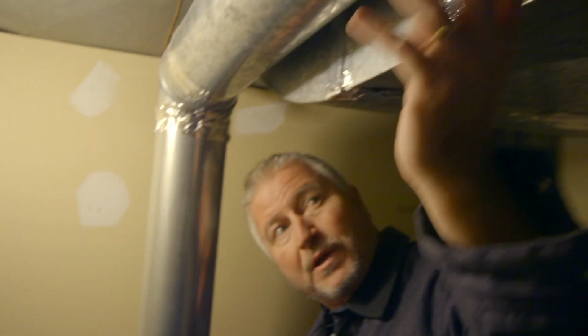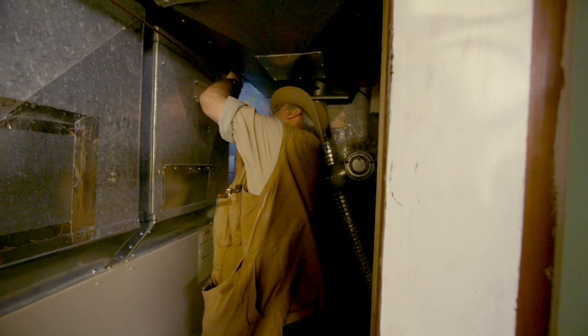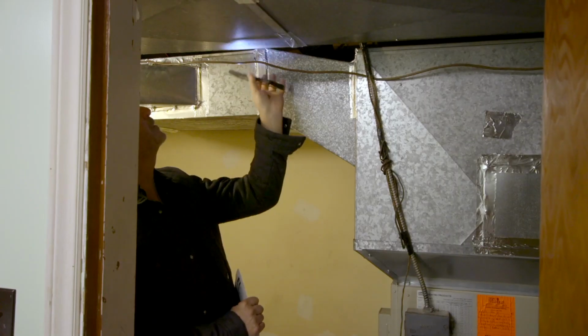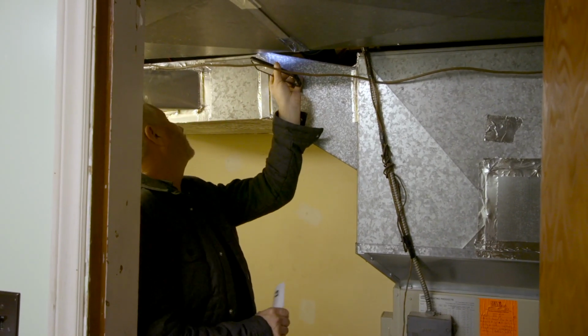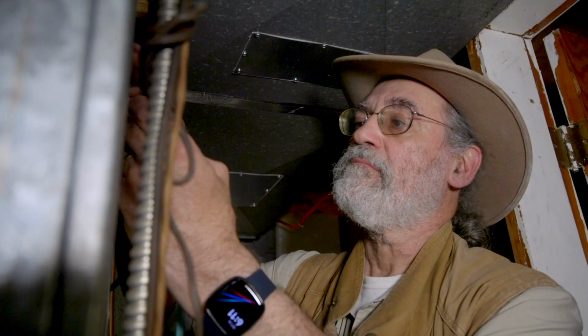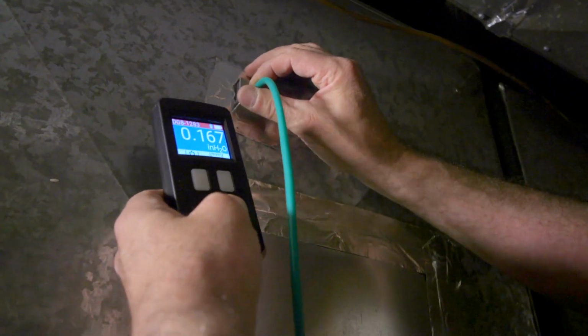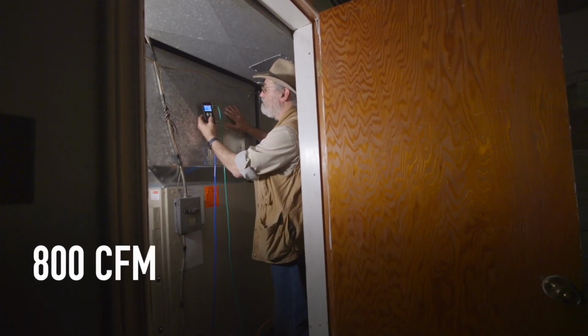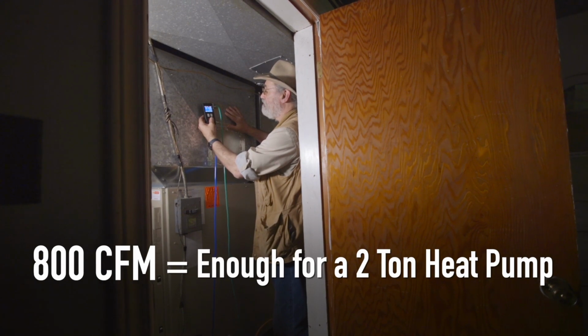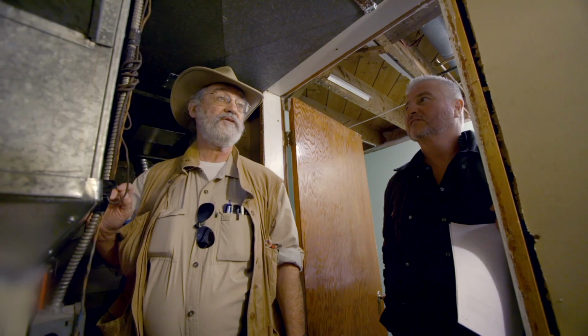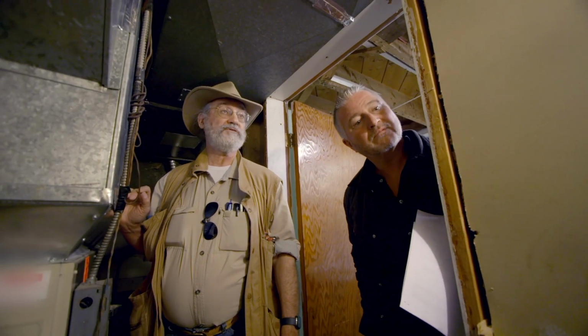So we went down to the furnace. Nice big return ductwork. One lead coming off the top. And then we measured the airflow and pressure in the ductwork, and figured out that it was moving around 800 CFM, which is enough for a 2-ton heat pump, which is a little small for this house. From a heating point of view, a 3-ton heat pump would be exactly the right size.